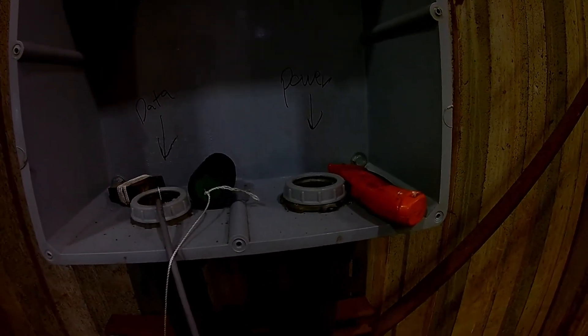Here's the problem. We've got a junction box on the west side of the building. It has a 1½ inch conduit going down to the floor and across to the other side, where it comes up to another junction box. We've tried a fiberglass tape and a steel fish tape, and every time we go through it from either side, it keeps getting hung up going through all the angles.